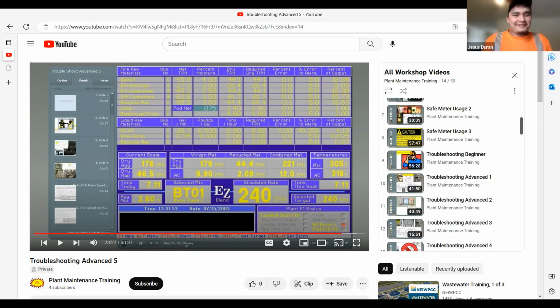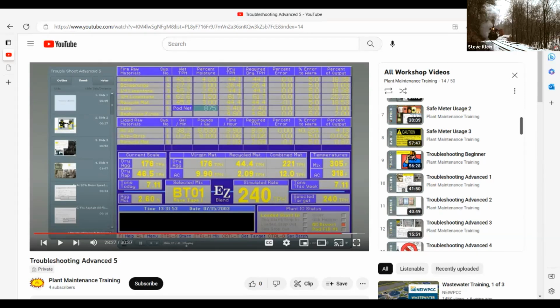All right. Yeah, I don't really feel a whole lot on that end. The simple explanation is it's a black box. You feed information in, you get information out. The information you're feeding in is RPM and temperature. What's coming out is tons per hour. And you know enough now to look and see: am I putting all oil in or am I putting air and oil in? Is the speed tach hooked up and running, giving me a signal? Is the temperature probe in its well and giving me a signal? That's what you need to look for.